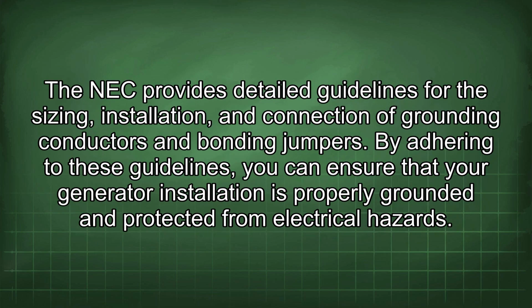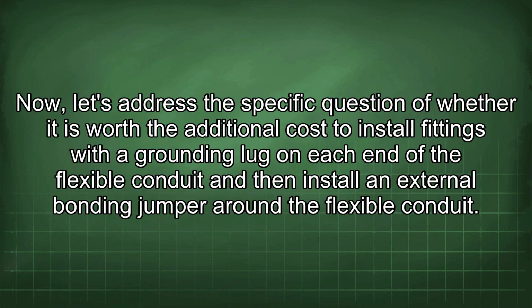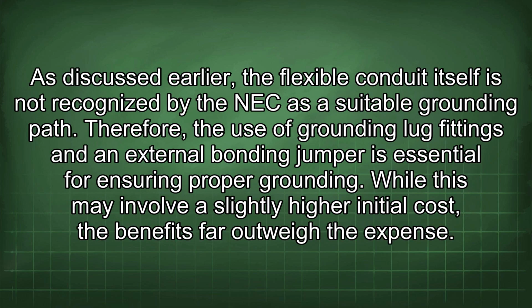The NEC provides detailed guidelines for the sizing, installation, and connection of grounding conductors and bonding jumpers. By adhering to these guidelines, you can ensure that your generator installation is properly grounded and protected from electrical hazards. Now, let's address the specific question of whether it is worth the additional cost to install fittings with a grounding lug on each end of the flexible conduit and then install an external bonding jumper around the flexible conduit. As discussed earlier, the flexible conduit itself is not recognized by the NEC as a suitable grounding path. Therefore, the use of grounding lug fittings and an external bonding jumper is essential for ensuring proper grounding.